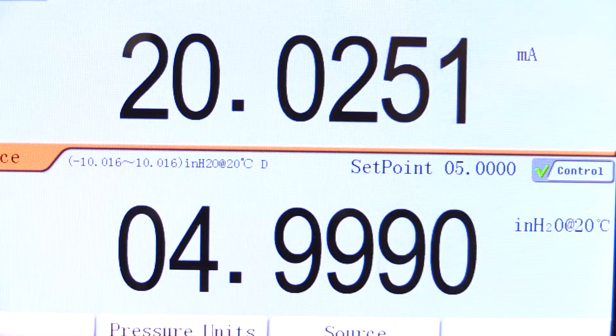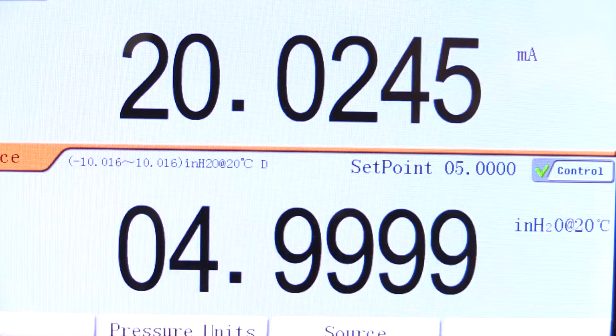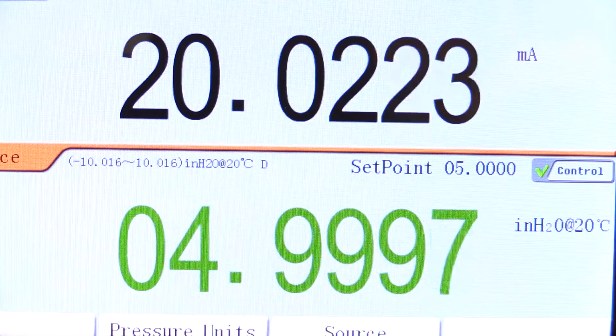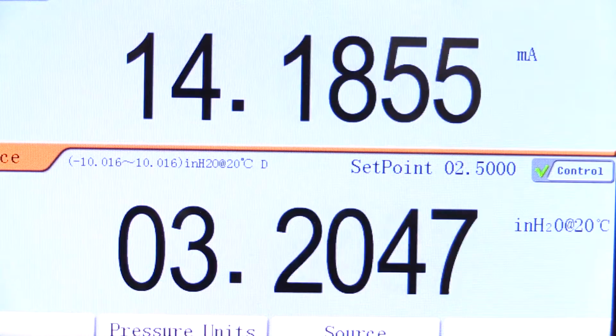In this example, all calibration points are manually entered, and data would be manually recorded. We will run this test ascending and descending to determine any hysteresis error.